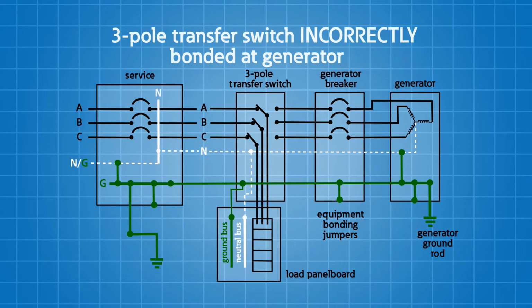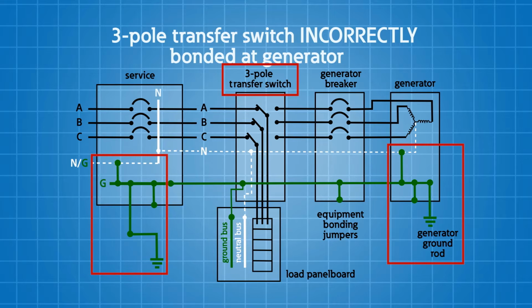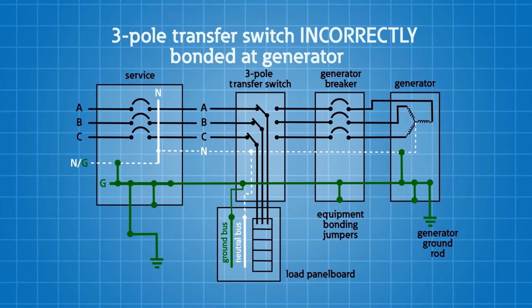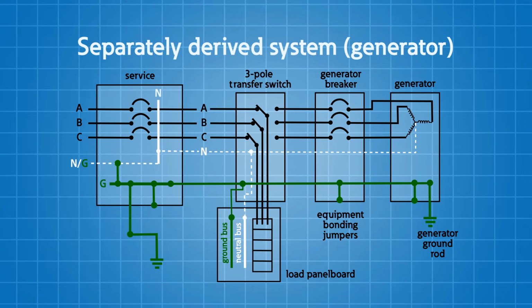And if you're bonded in the generator and you're not switching the neutral, you have two separate areas where that neutral conductor is being bonded, and you could have circulating currents. You could cause GFCIs or ground fault protection of equipment not to work and function correctly. A simple fix, if you didn't buy the right transfer switch, a 3-pole transfer switch, and you bonded that neutral in the generator, is to just lift the bond in the generator. Your generator instructions will tell you how to do that.